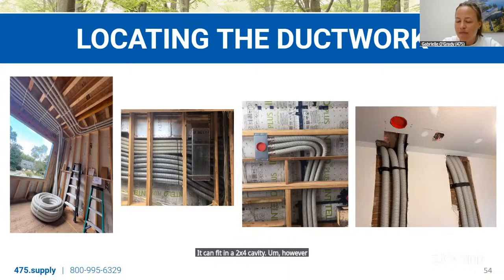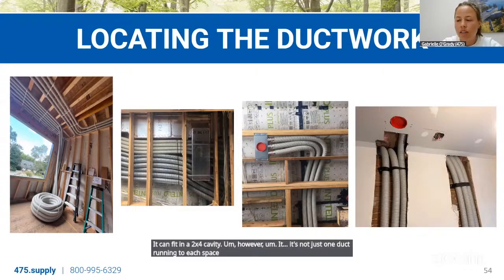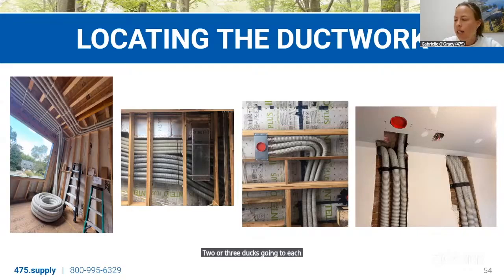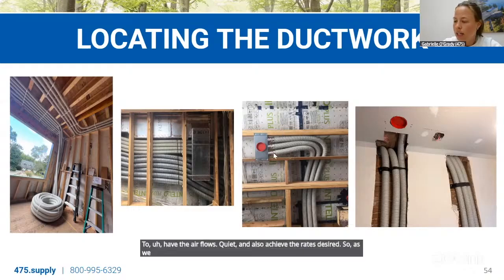However, it's not just one duct running to each space in order to get the exhaust rates and supply rates that we need. It could be 1, 2, or 3 ducts going to each diffuser in order to have the airflows quiet and also achieve the rates desired. So as we can see in this third photo, we have 3 ducts going to this location. That would be more typical of maybe a kitchen space.